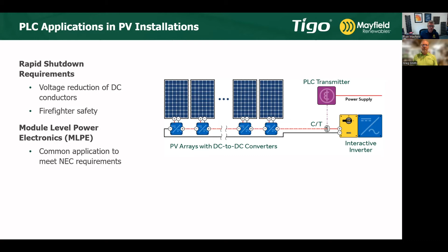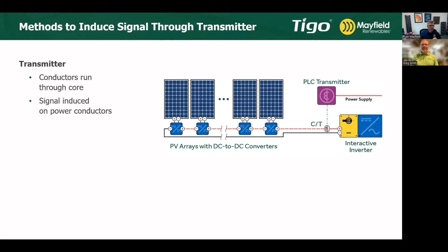The conductors are run through the core. We'll get into how many conductors and some installation specifics, but just to set the stage: we have conductors, we have some sort of transmitter with a power source. This can look a lot of different ways - it's integrated in the inverter, or external to the inverter. We're showing it all external, but there are plenty of options where it's integrated in. So the conductors are coming in, and that signal gets induced onto the power conductors.